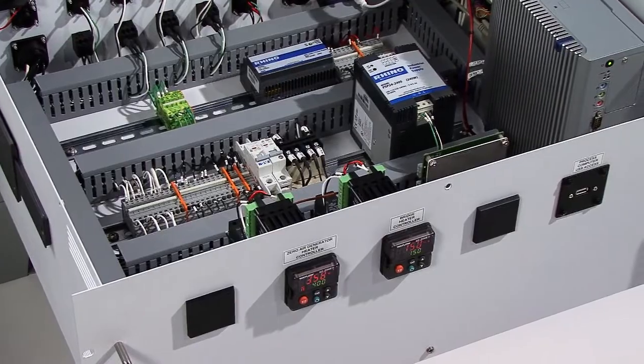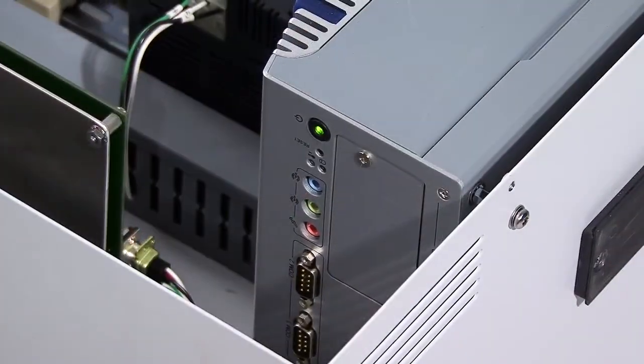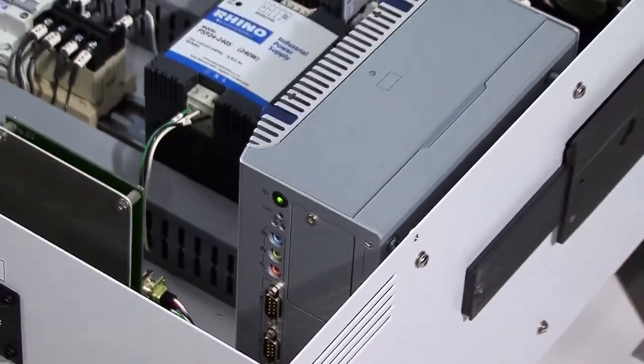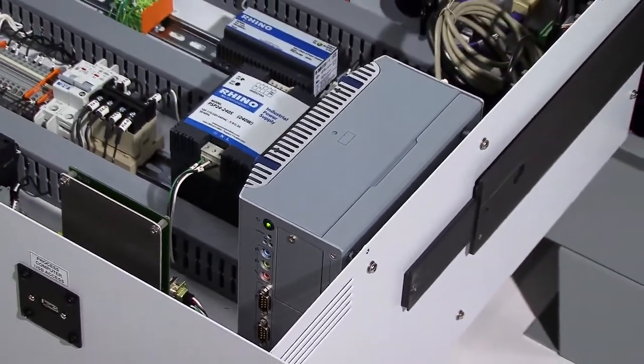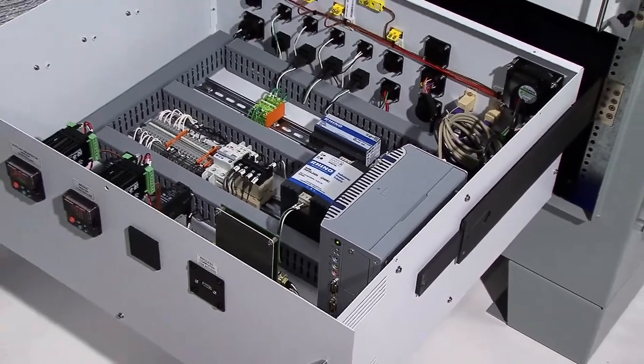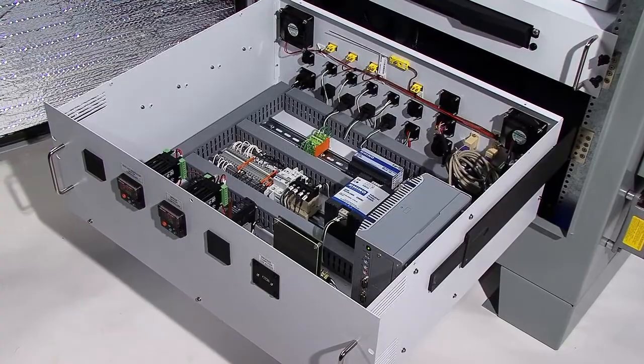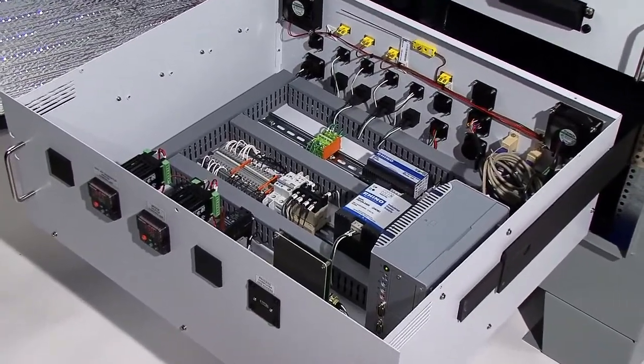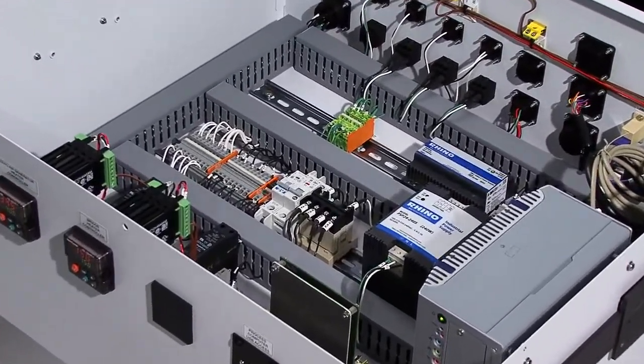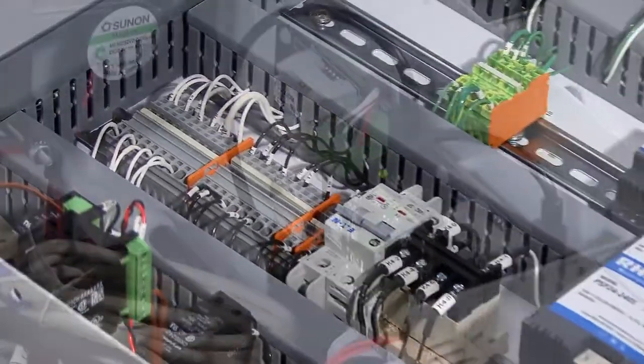Here in the pullout electronics bay we have a power supply, a ruggedized industrial PC running Windows 7 with a secondary hard drive that has automatic continuous backup. We also see various analog connections to monitor cabinet and sample system parameters as needed, temperature controllers, in addition to discrete outputs required to drive sample system multiplexing valves, pressure transducers, and other application-specific hardware.